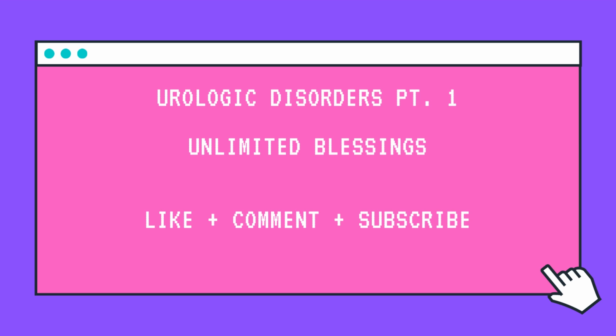To determine whether a patient is emptying his or her bladder, the amount of urine remaining in the bladder after voiding, residual urine, must be measured. A bladder scanner can be used to measure post-void residual, PVR. This procedure may be diagnostic, but it is often part of a bladder training program for patients who have lost control over bladder function. Residual volume should be measured immediately after voiding. Occasionally, patients are catheterized to measure residual urine. Less than 50 milliliters of residual urine is considered normal.